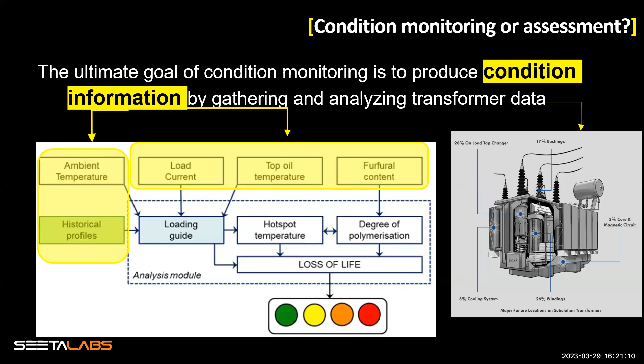I'm giving you a real life challenge we face every day. We have to give a techno-economical justification, show a confidence limit, and confidently state what fault is currently incepting and how long it will take for this fault to convert into a failure mode. At the end of the day, the transformer might stop working, so we need to take action within a stipulated period of time, which is where my company, or what we do in general, steps in.